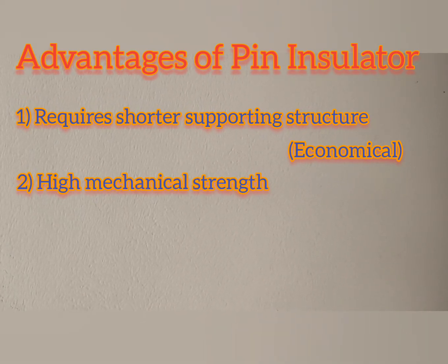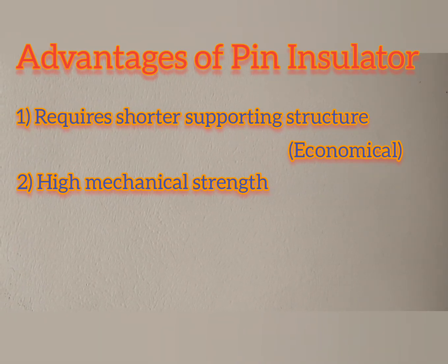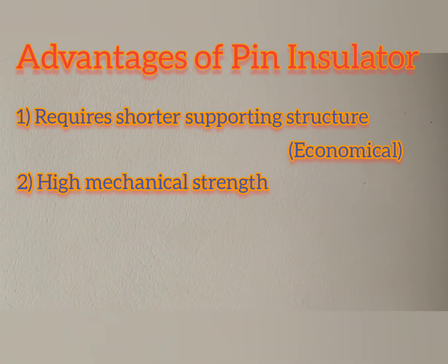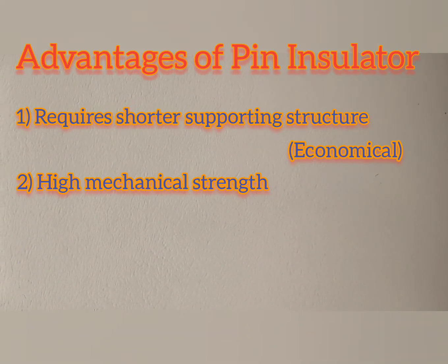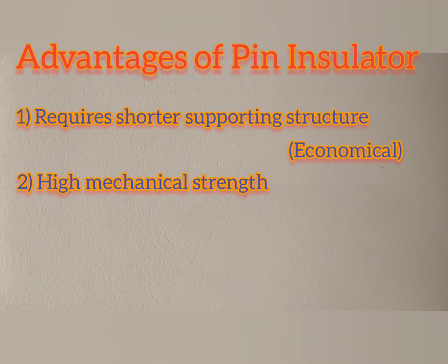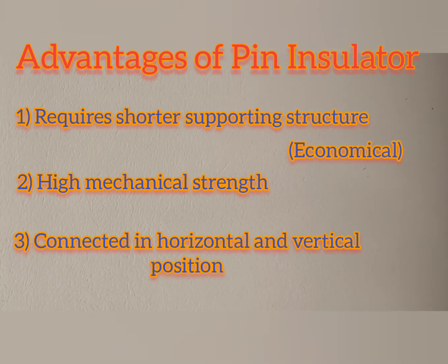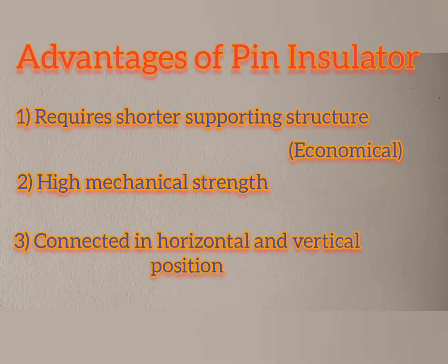Second advantage is mechanical strength of pin insulator is high. Here, multi-piece units are used in high voltage. One advantage of using several units of insulator is that defect in one petticoat or rain shade doesn't affect the mechanical strength of insulator and it continues to function with full capacity. Next advantage of pin insulator is it can be connected in horizontal as well as vertical position.